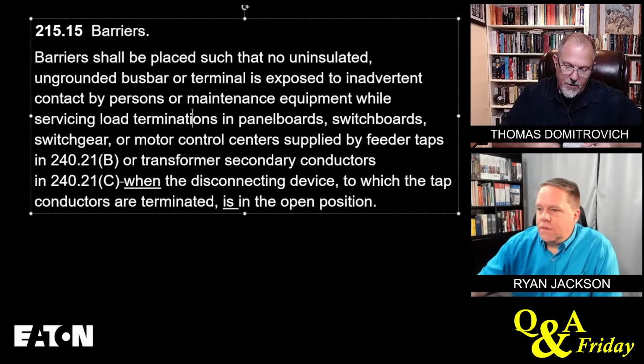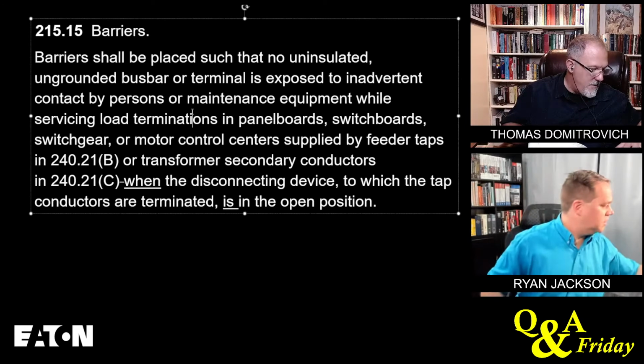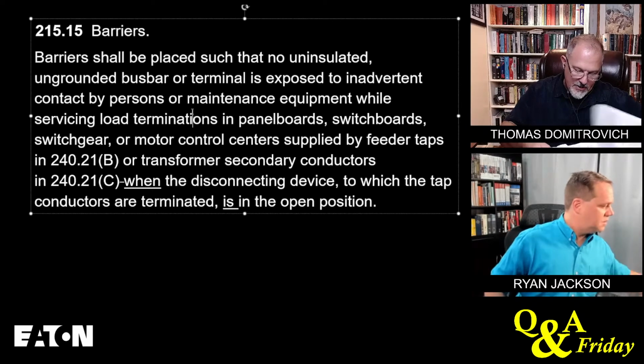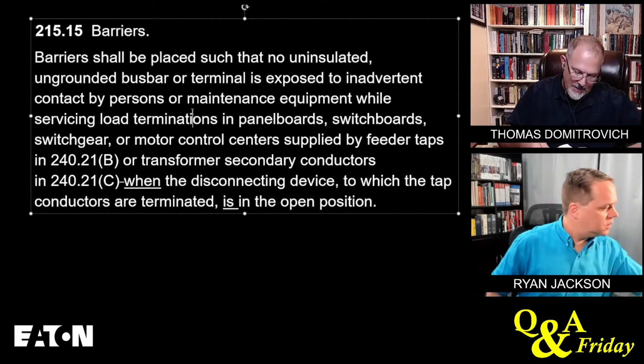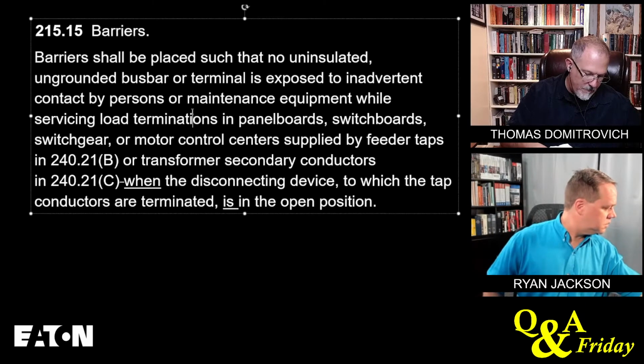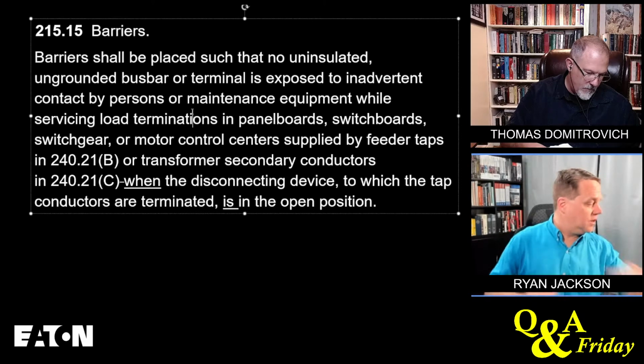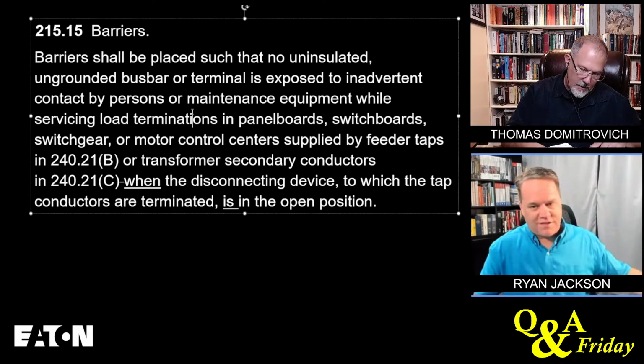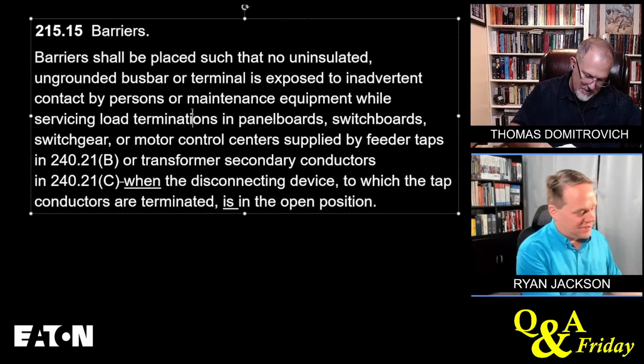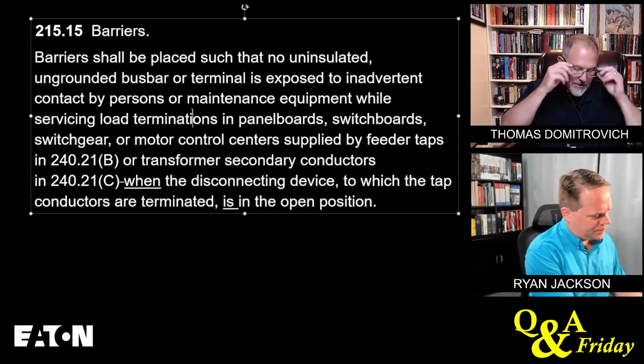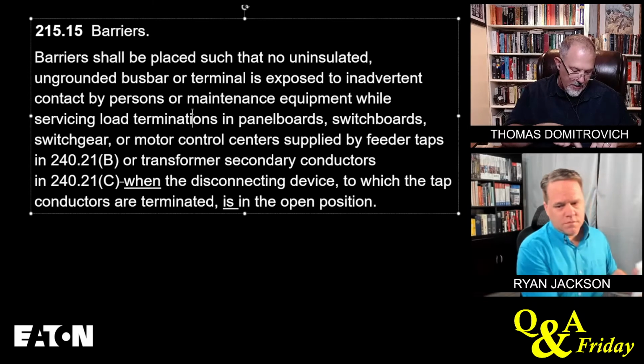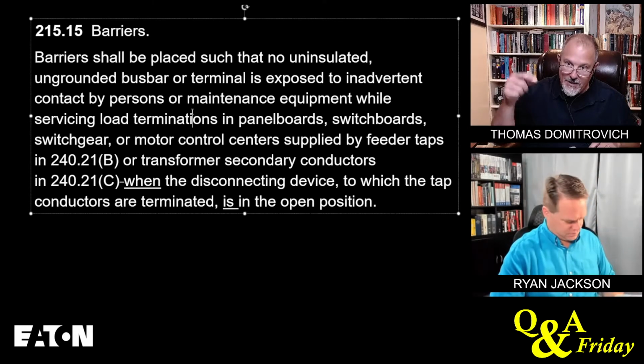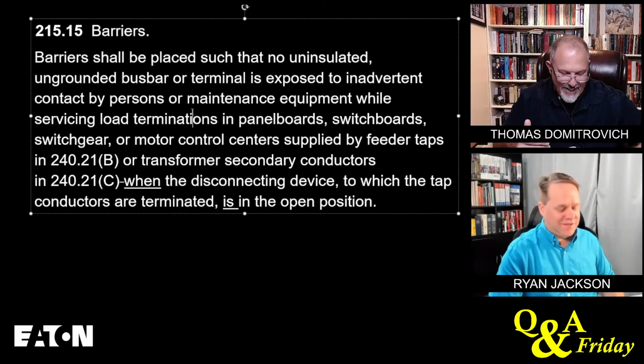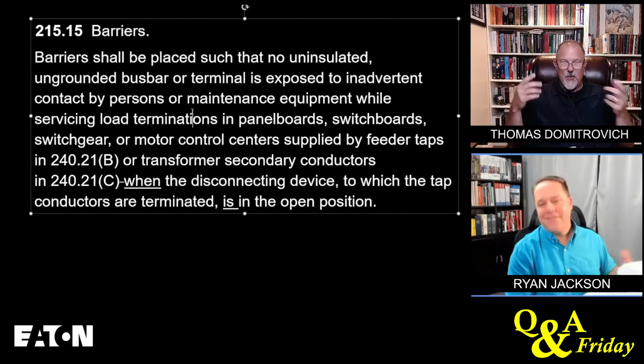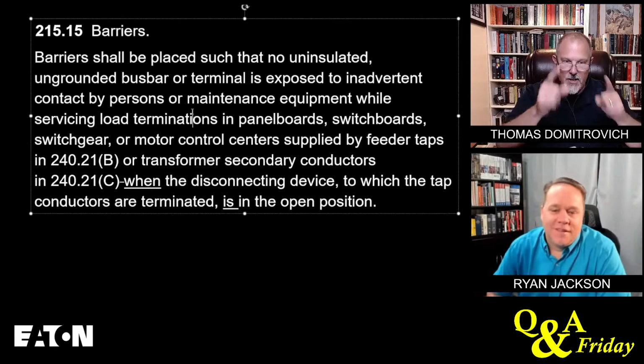Yeah, let's just double check your math. I probably should. 230.62C. It sounds right, but I've learned that I can't trust my memory. Oh, tell me about it. Especially when the sections change every 3 years, you have to forget what you've learned and then relearn it. Yeah. So if you look at 230.62, it says enclosed or guarded energized parts. So in the parent text of 230.62, it said energized parts, and then in C, it talked about the barriers. So when we moved that language over, we did not bring over energized.